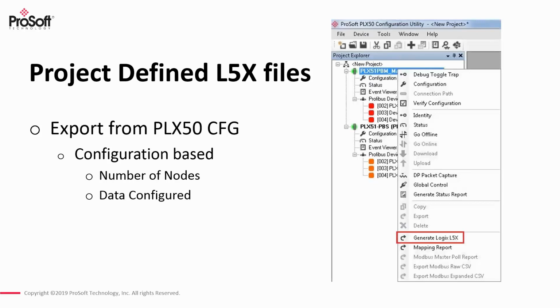For Profibus master projects, one of the things that we've implemented within this module is the ability to generate Logix L5X files. And so this would be based on the Profibus configuration of the network. So essentially you utilize this PLX50 configuration utility to tell the Profibus master module what devices are out on that network and how much data to grab from each one of those devices.